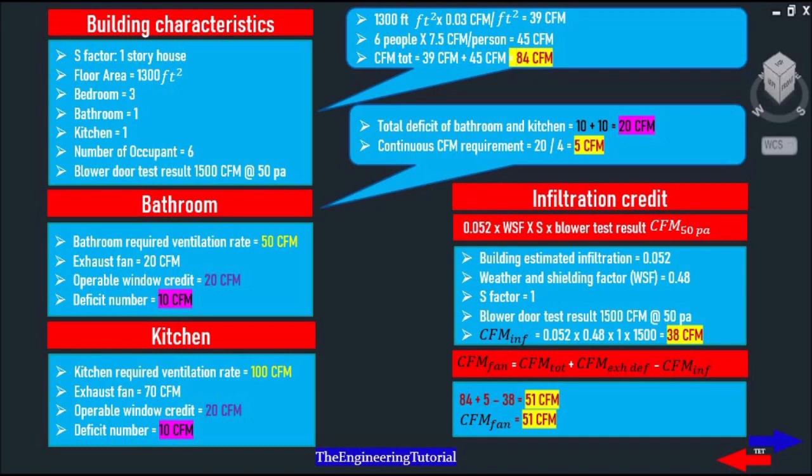Our first step is to calculate the total desired ventilation rate and the first part of the equation deals with the floor area. We multiply the 1300 square feet by 0.03 that gives us 39 CFM. For the second part we need to now consider the number of occupants. As we know there are 6 occupants so we will multiply 6 occupants by 7.5 CFM per occupant that gives us 45 CFM to deal with the contaminants which are generated by occupants within the building. So we need to now add them together 39 plus 45 that gives us a total required ventilation rate of 84 CFM.